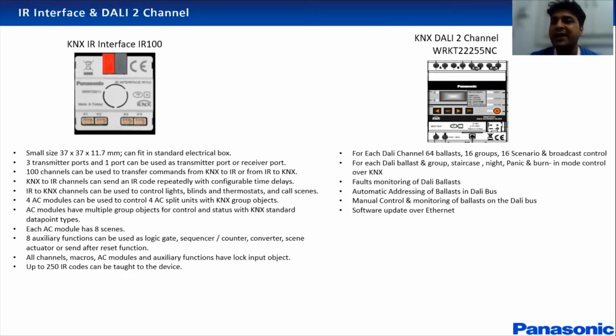We also have a 2-channel DALI gateway. Each channel can configure up to 64 ballasts. You can create 16 groups and 16 scenarios. Fault monitoring is also available. You can automatically address the connected DALI ballasts, and you have an option to update the software of the DALI gateway using an Ethernet port provided on the gateway itself. Manual override buttons and monitoring of the channels on the ballasts are possible using the onboard keys available on the DALI gateway.